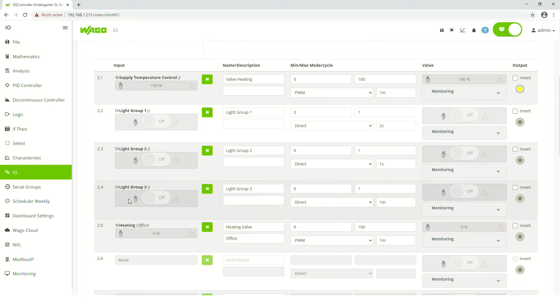Now our PID controller is ready engineered, and I will show you a very useful function: a commissioning help. With this commissioning help, you will be able to select some data points, for example the room temperature, the set point, and the heating valve, and immediately check your functionality in a graphical way. That is, I believe, a very good and helpful function.